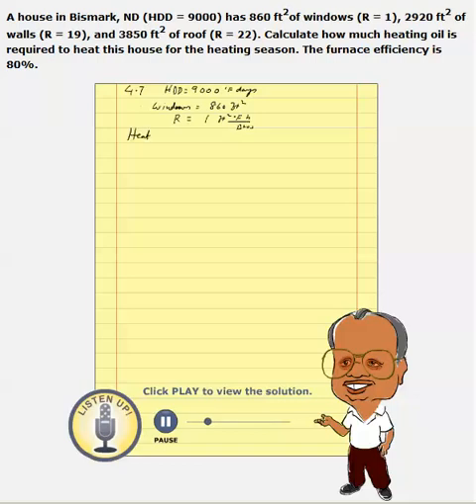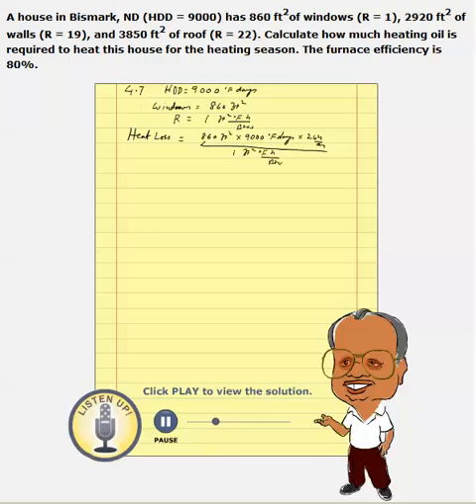So we can calculate heat loss through windows. All we need is the area — 860 square feet — times HDD, which is 9,000, times 24 hours in a day, divided by the R-value of 1. The units cancel out — square feet, degrees Fahrenheit, and hours — and the total heat loss through windows is 185,760,000 BTUs.